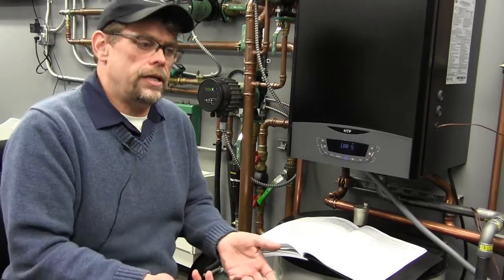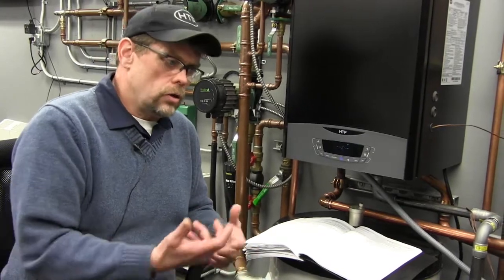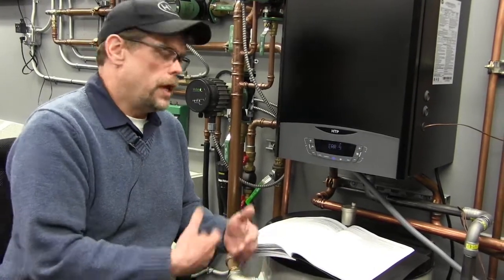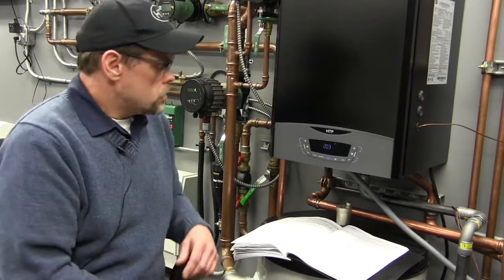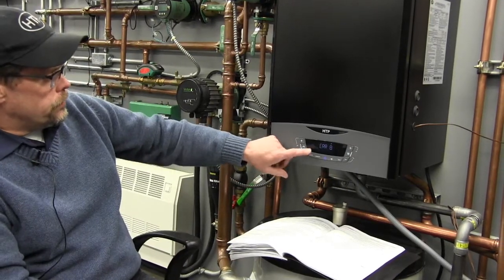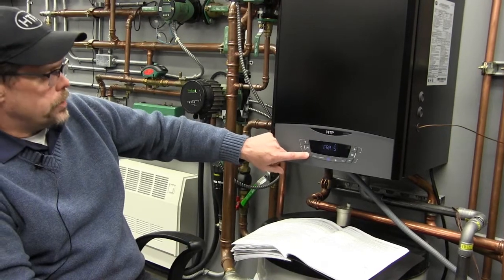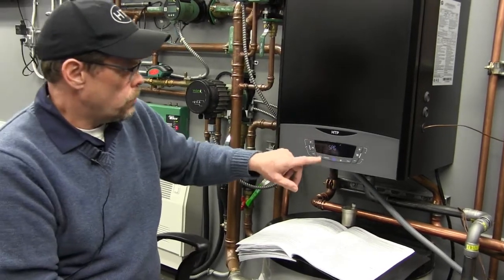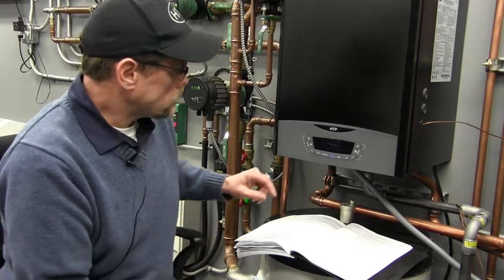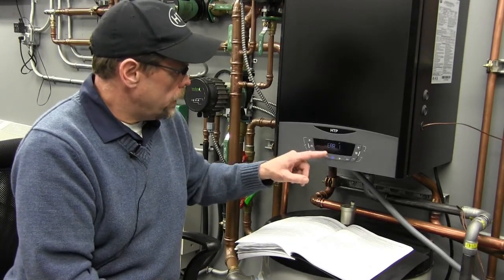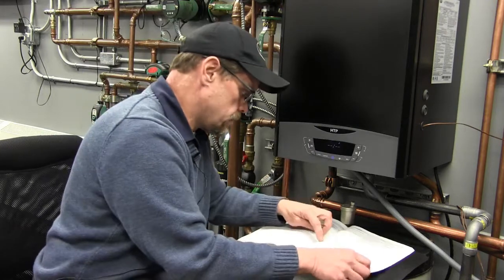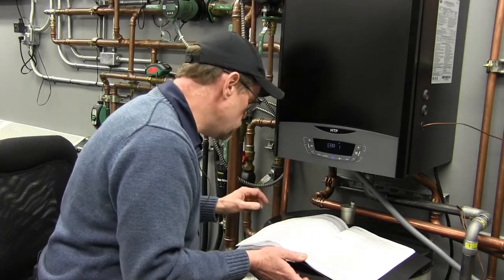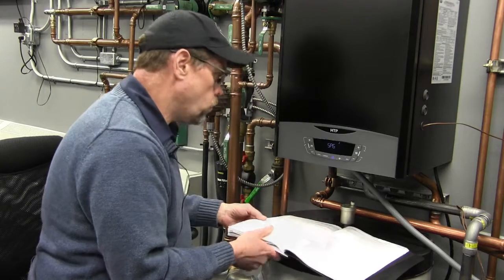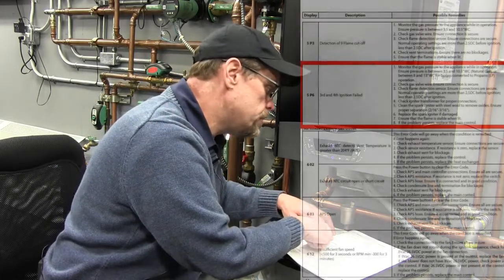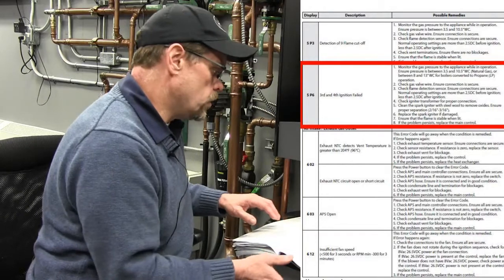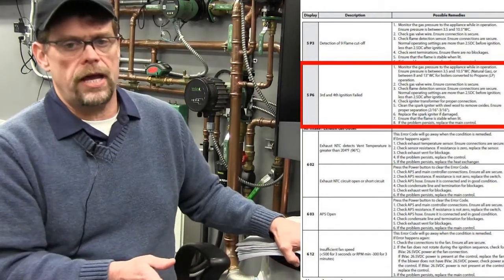So as soon as we engaged to go into run mode, the control immediately recognized there was no sensor and went into an error code. So we can navigate through the different codes, error 8, 7, 6, 5, all the way back down to the first error, error number 1, and it's showing error 1 is 5P6. So again, I go to my error code and I find 5P6 on page 83, and it lets me know that the third and fourth ignition had failed.